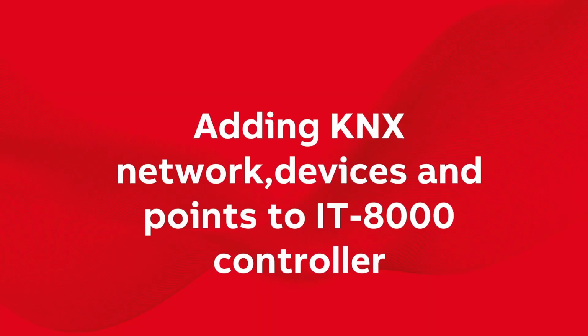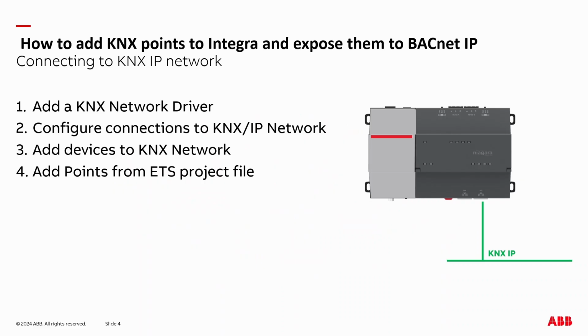In the following example, I will be working on a live IT 8000 controller to demonstrate how to configure KNX part of this exercise. The first stage is to configure KNX network in the Integra Workbench software. The main steps for this process are adding a KNX network driver, configuring connections to KNX IP network, adding devices to KNX network, adding points from ETS project file.